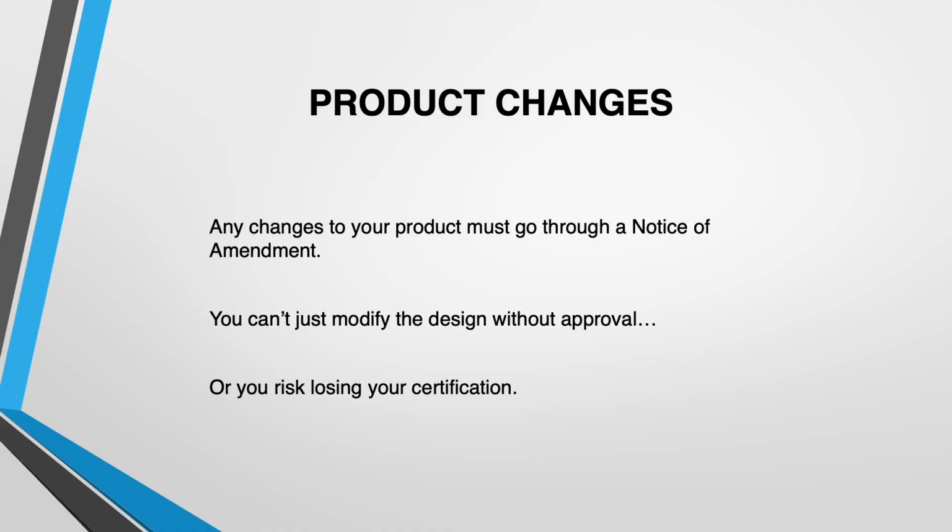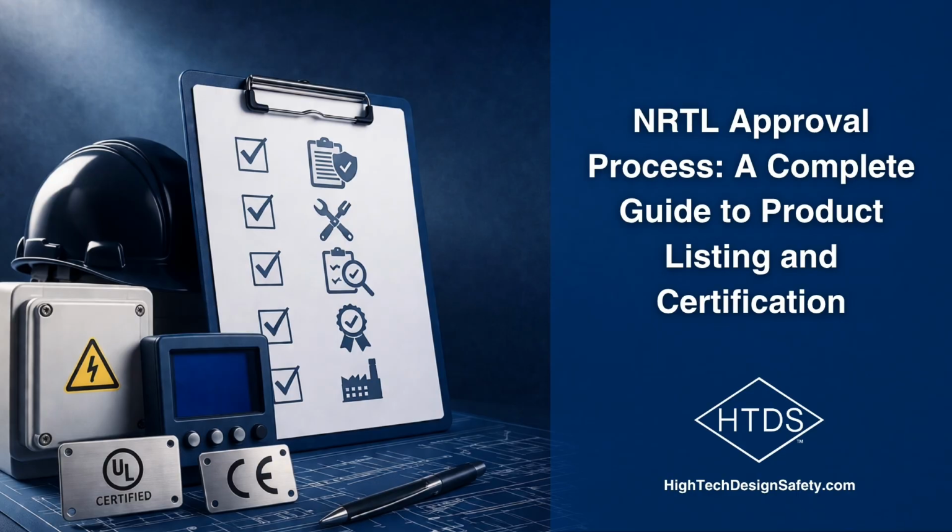Any changes to your product must go through a notice of amendment. You can't just modify the design without approval, or you risk losing your certification. The NRTL approval process is detailed, but when done correctly, it ensures your product is safe, compliant, and ready for market.